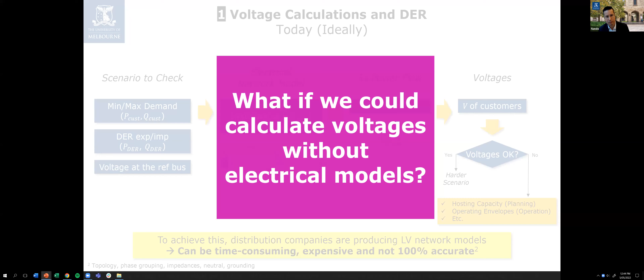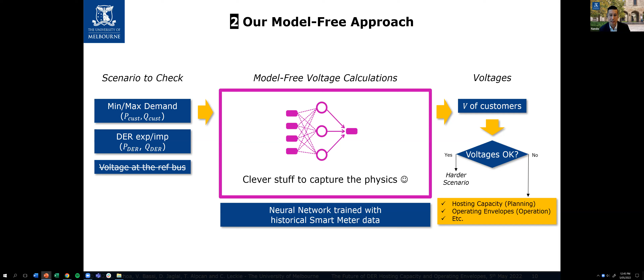In terms of a scenario, you still have to define the scenario for which you want to calculate the voltages, and you will assess and create harder scenarios. But instead of power flows and having the electrical model, now we have some clever stuff that captures the physics of the low voltage network. We're using neural networks trained with historical smart meter data. The advantage is that it removes the time and cost associated with producing LV models, and can also be an extremely quick alternative to power flow based techniques.